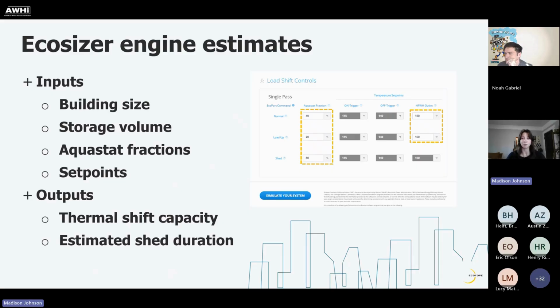Users go to Ecosizer and input system characteristics like building size, storage volume, aquastat fractions, and set points. Then the simulation tool outputs the system's thermal shift capacity and estimated shed duration. The thermal shift capacity measures the difference in stored energy from when the heat pump turns off in load up to when the heat pump would be triggered to turn on during shed operation. So thermal shift capacity translates to the volume of supply temperature water that the system can deliver during a shed period without the heat pump turning on. This metric is calculated based on the storage volume, aquastat fractions, and set points.